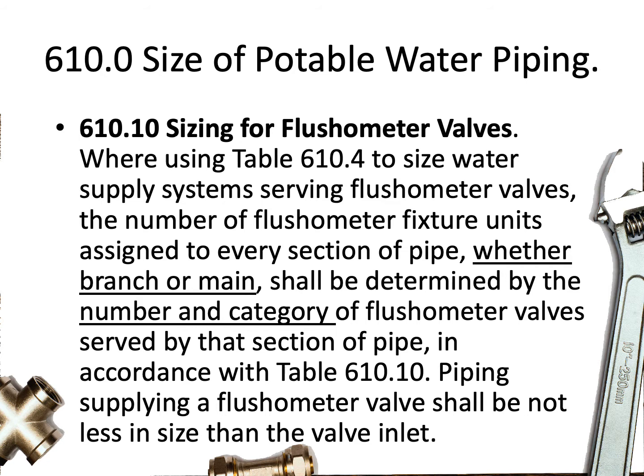The second point is that the fixture units we give to flushometer valves are not always the same — they can change depending on what part of a system we are at. Sometimes you'll see a flushometer valve on a branch valued at 40 fixture units, but by the time you get back to a main riser or the water service or the building supply, that same flushometer valve will only be worth 10 fixture units. So they can decrease and change values as you progress through a building, and we'll explain that in this video.